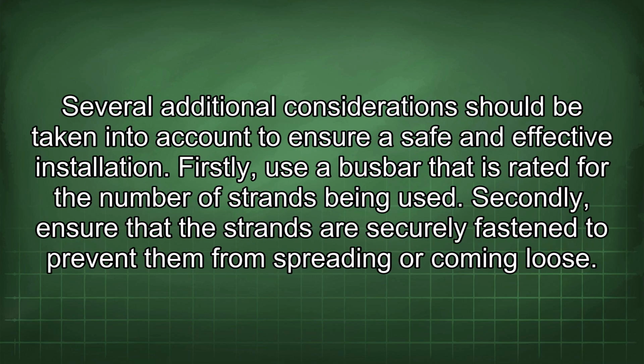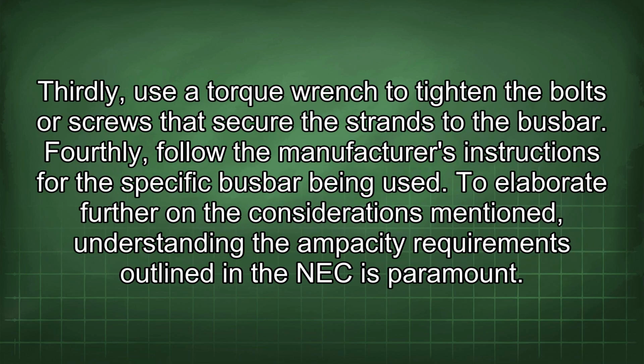Several additional considerations should be taken into account to ensure a safe and effective installation. Firstly, use a busbar that is rated for the number of strands being used. Secondly, ensure that the strands are securely fastened to prevent them from spreading or coming loose. Thirdly, use a torque wrench to tighten the bolts or screws that secure the strands to the busbar. Fourthly, follow the manufacturer's instructions for the specific busbar being used.